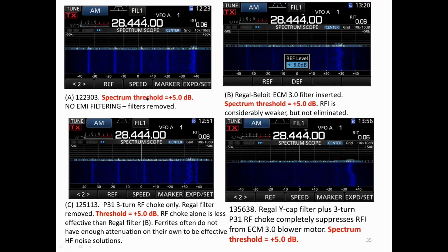Now, let's look at this again. Here's the spectrum threshold at 5 dB with no filters. Again, this is for the furnace alone. The AC is off. Here's the RFI when the Regal filter is in place. Again, that's a 2-capacitor common mode filter, which attempts to shunt the RFI to ground right at the entry point for the power lines to the ECM motor.